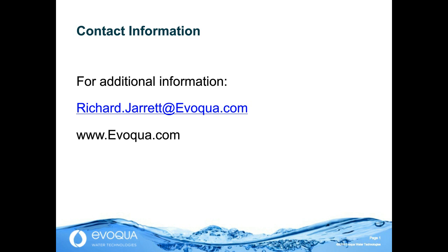So the appropriate added component, and ultrafiltration is going to be common here, is that a UF module could be added to assure attainment of endotoxin and the low microbial level required for water for injection. So I think that although many complete new systems of the membrane type will go in, I think it's logical that purified water will be a source for production of water for injection, and then only those components needed will be added. So I think it can prove to be quite practical.